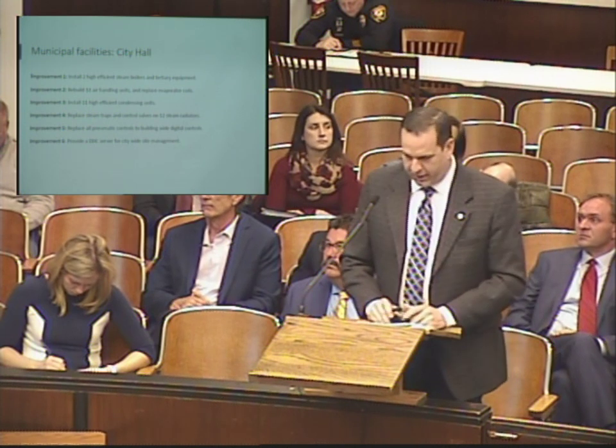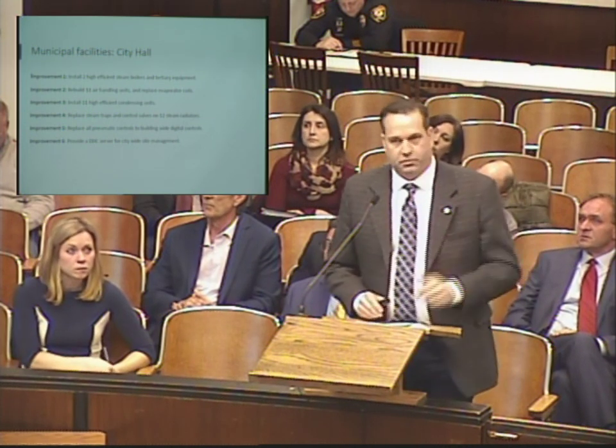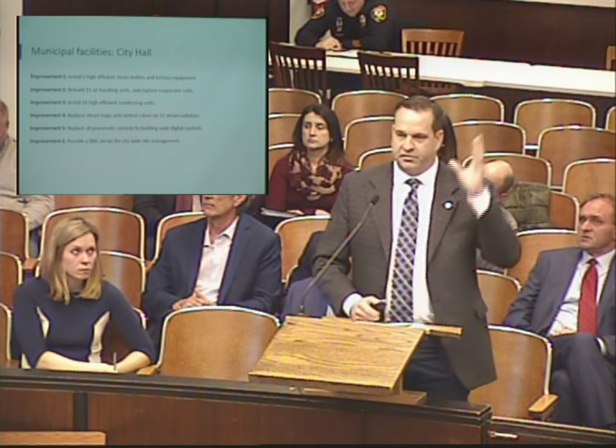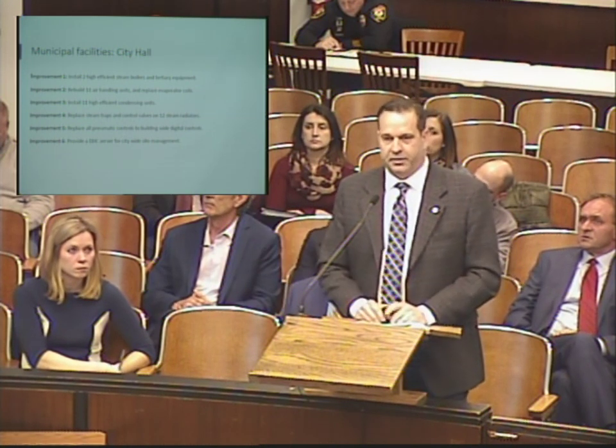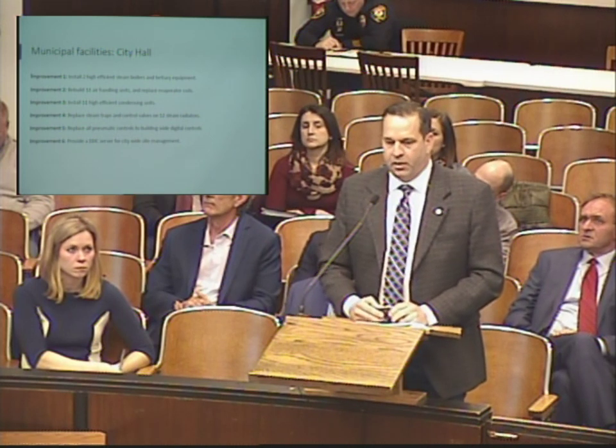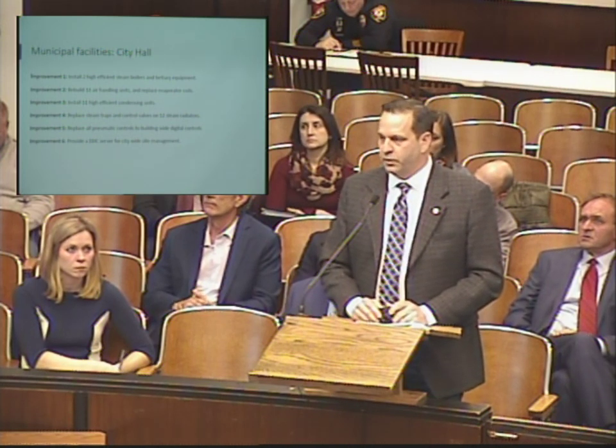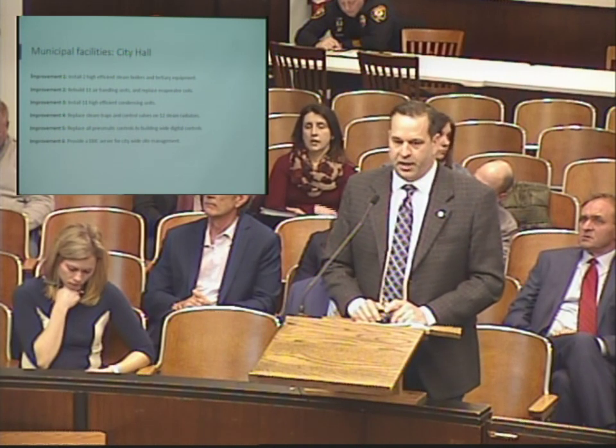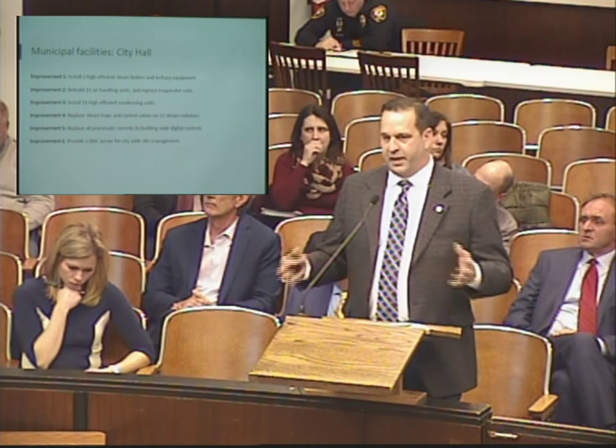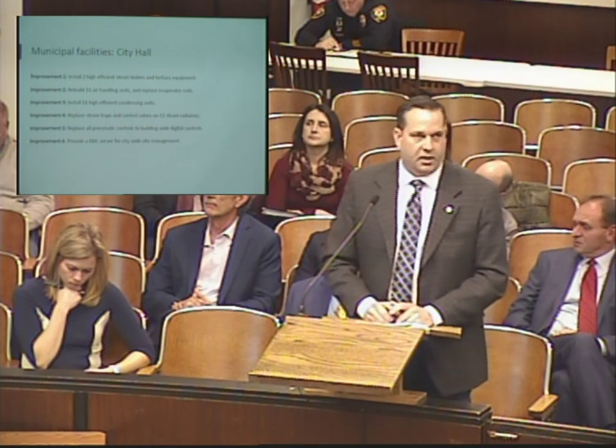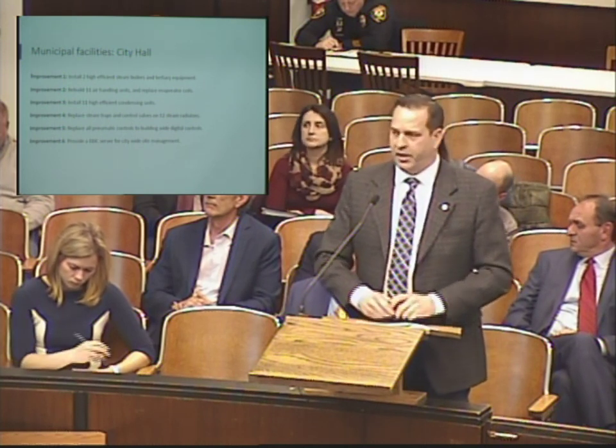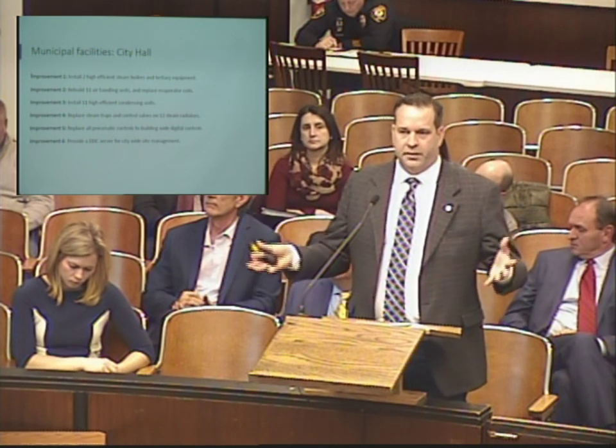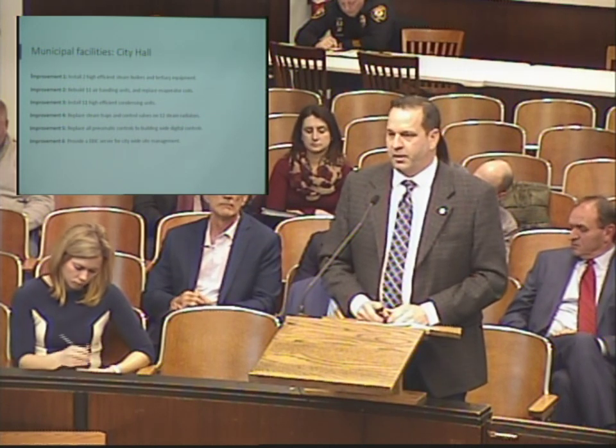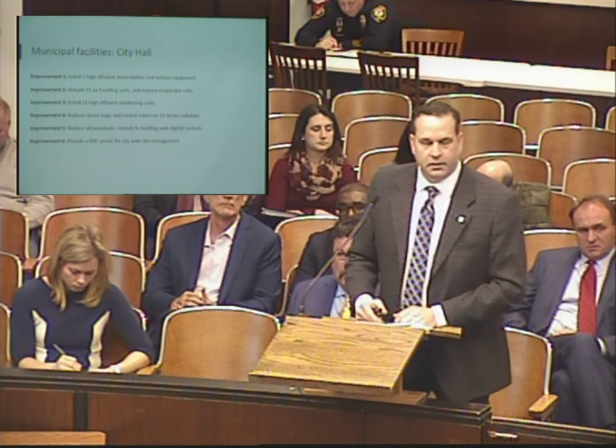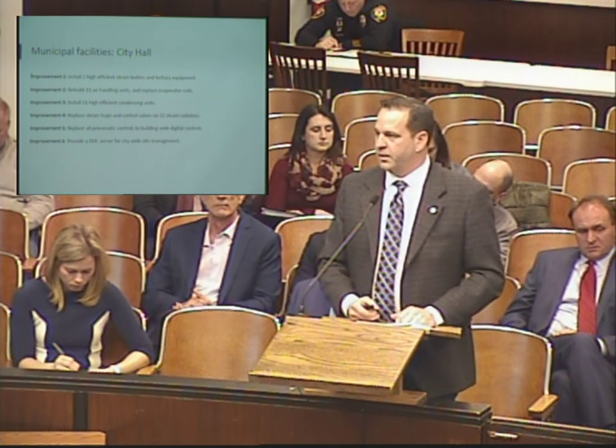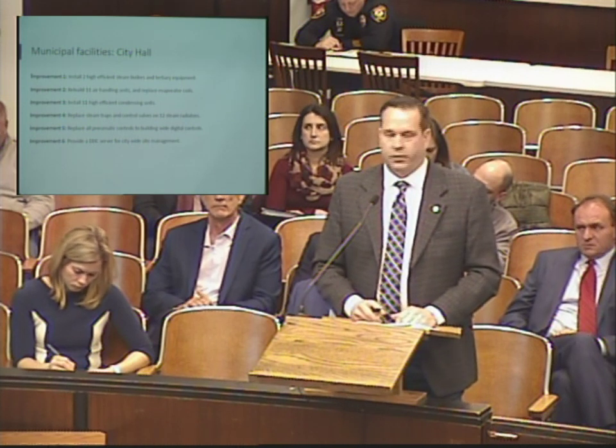The next thing is the current air handling units throughout the building, tucked away in mezzanines, closets, and other spaces. We looked at a couple of different approaches. The most feasible was to rebuild these air handlers rather than supply new ones, which would be larger, take up more space, and cost a lot more. So we're proposing to take all the components and replace them in the existing air handler, essentially making it new, since an air handler is really just a fan in a box. All the internal components will be rebuilt or replaced, along with the controls.